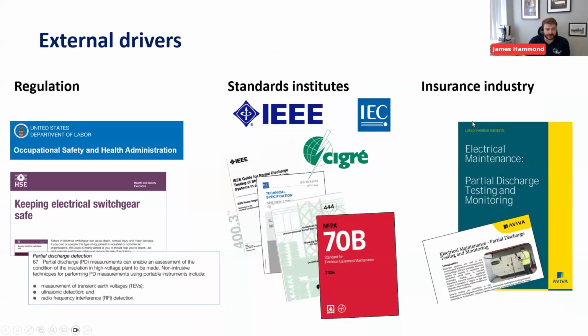There's also a lot of external drivers as well, you can see a few marked here. The occupational OSHA pushes towards PD testing, keeping engineers safe - one of the most important parts of PD detection really. In the UK we have the HSE, again mentioning partial discharge.